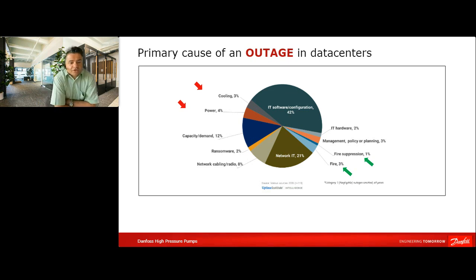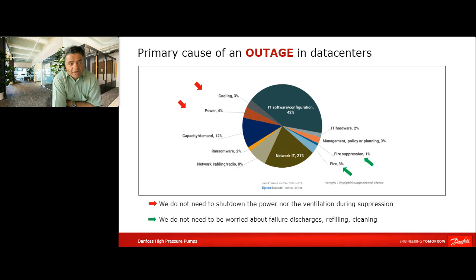One major thing, talking about the cooling and the power: when you have installed a high pressure water mist system in your data center, this is for sure an approved system. And when it is an approved system, you can also be sure that these approvals have been done by running the ventilation inside the data center building, and also with all the servers under power. So you don't need to shut off the electricity. All the servers can remain energized, and the ventilation can continue working while you extinguish with high pressure water mist. This is a good advantage of this system compared to some others, which I come to later.